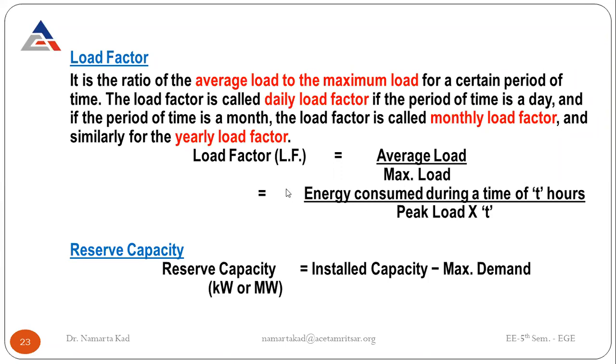There is one more formula for the load factor, that is, it is also equal to the energy consumed during a time of t hours. What is the total energy consumed? Like if we have to calculate the load factor for 24 hours, firstly we have to draw the chronological load curve, then we calculate the energy consumption. So the energy consumed during a time of t hours, t may be 24, divided by the peak load or maximum demand or maximum load, multiplied by t.